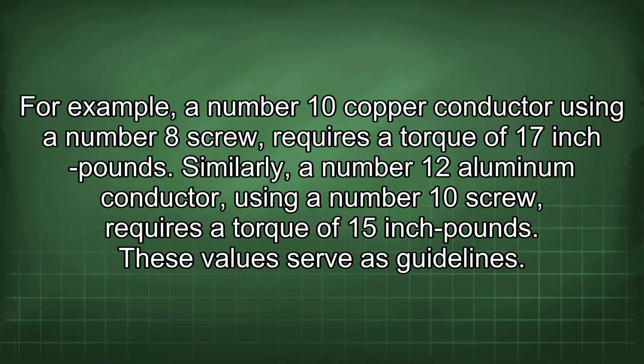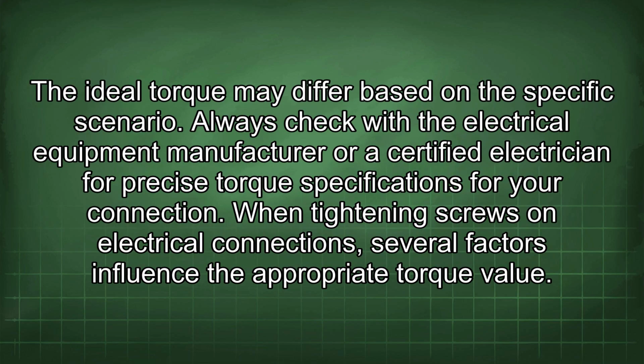For example, a number 10 copper conductor using a number 8 screw requires a torque of 17 inch-pounds. Similarly, a number 12 aluminum conductor using a number 10 screw requires a torque of 15 inch-pounds. These values serve as guidelines. The ideal torque may differ based on the specific scenario. Always check with the electrical equipment manufacturer or a certified electrician for precise torque specifications for your connection.